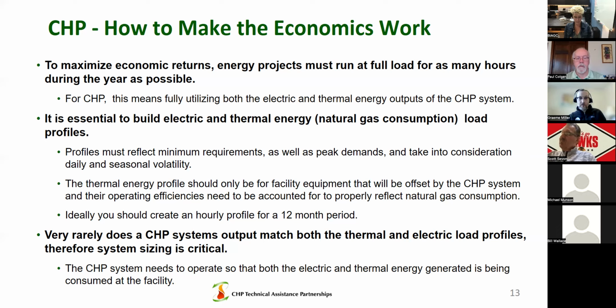The thermal energy profile should only be for facility equipment that will be offset by the CHP system and their operating efficiencies. So we would only count, in the case of your buildings, most likely the on-site boiler or steam generator providing process heating and domestic hot water. We wouldn't take into account any other thermal use that CHP wouldn't be able to replace.